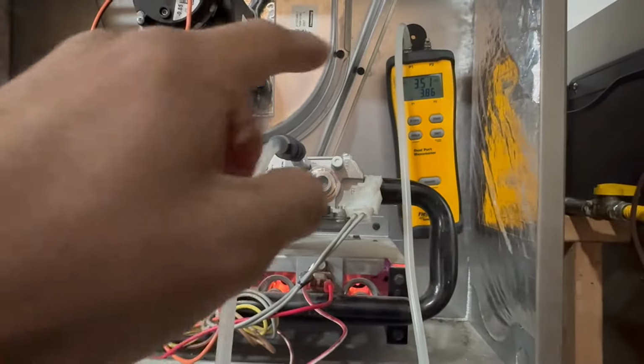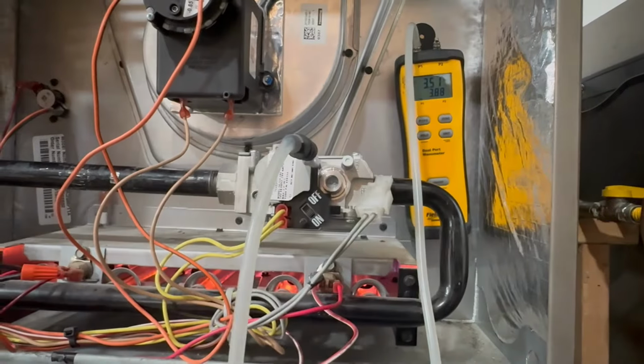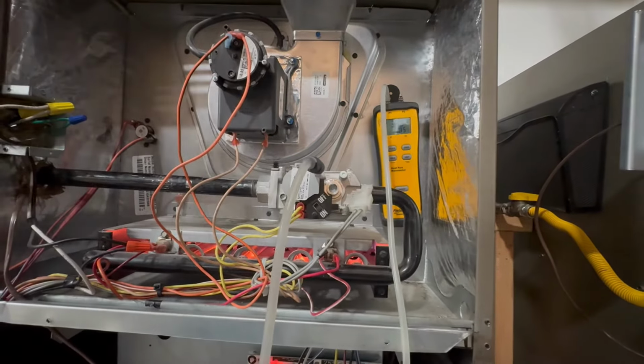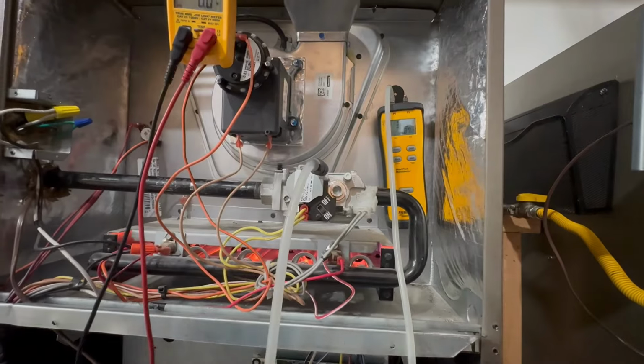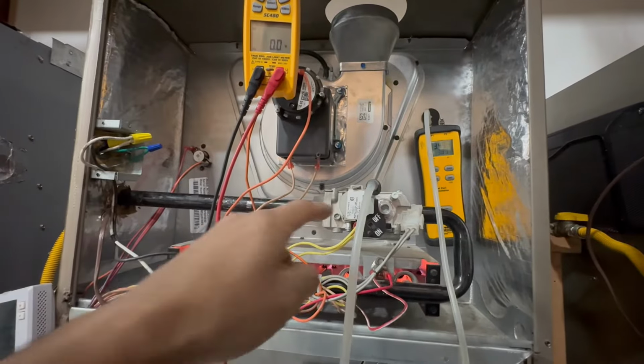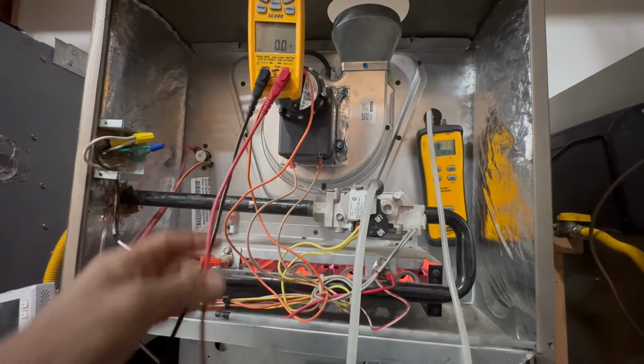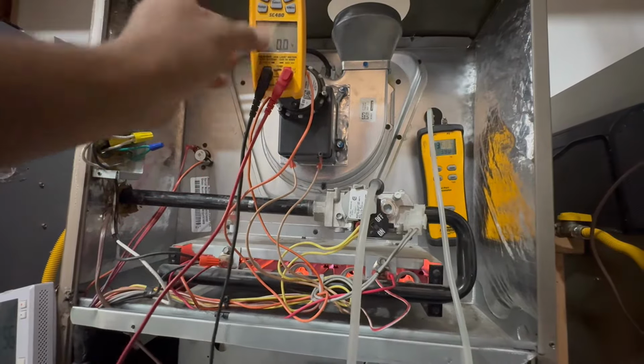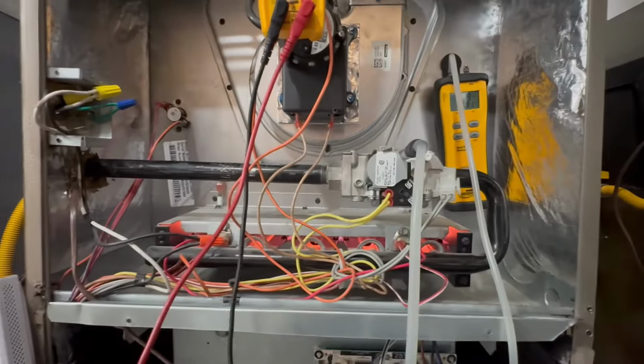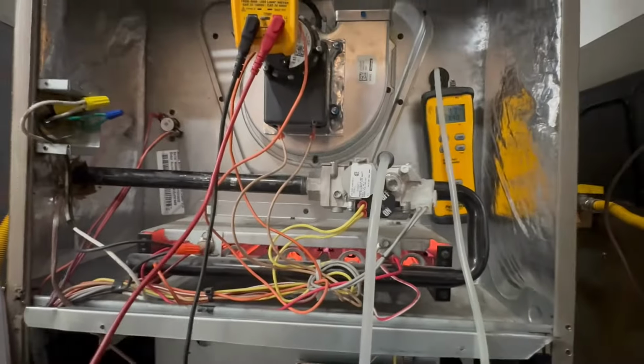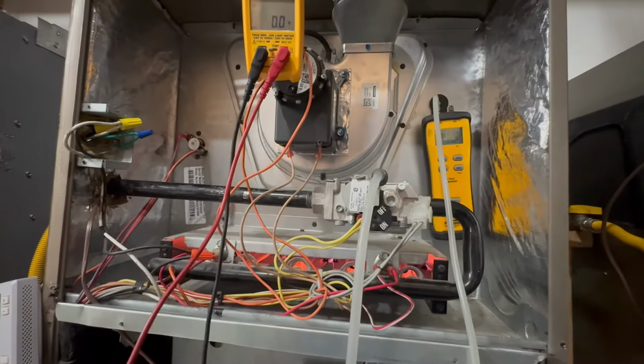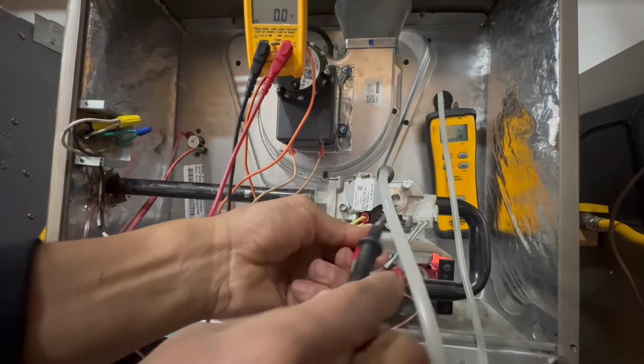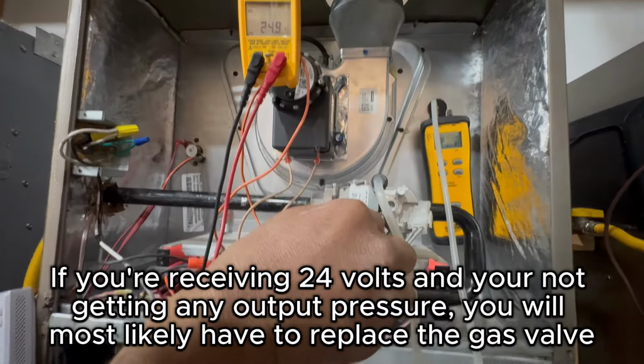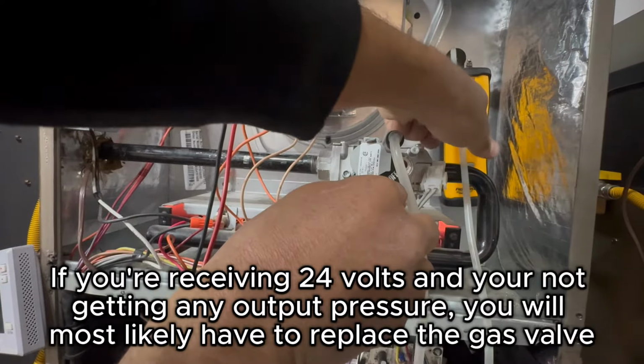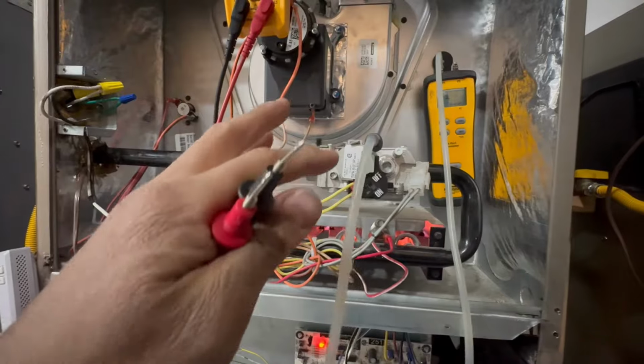But yes, you have to have a way to test the gas pressure. You need the little kit, the tubing. And another thing too, last thing, you want to make sure you have voltage going to the gas valve too. So remember, it can fail mechanically or electrically. So all you're doing is making sure you're getting 24 volts. On the two leads that are going there, all I'm going to do is put my leads in the back, and I have to have 24 volts. So you see right there, I'm getting 24 volts. And obviously I know I am because I'm getting some gas pressure and I have some flames. So that's how you will check this gas valve.